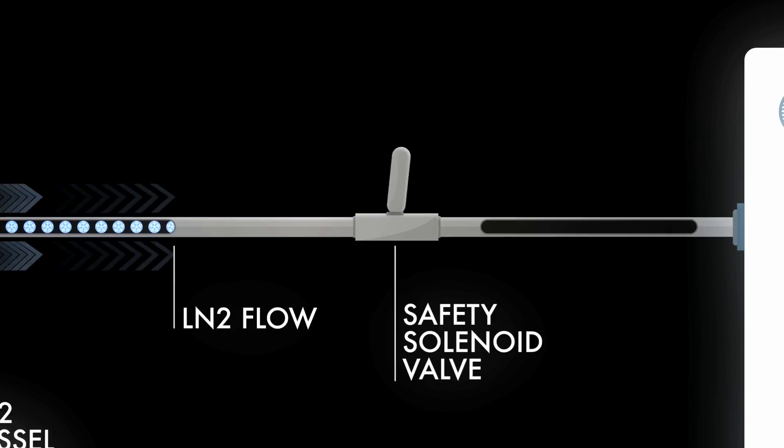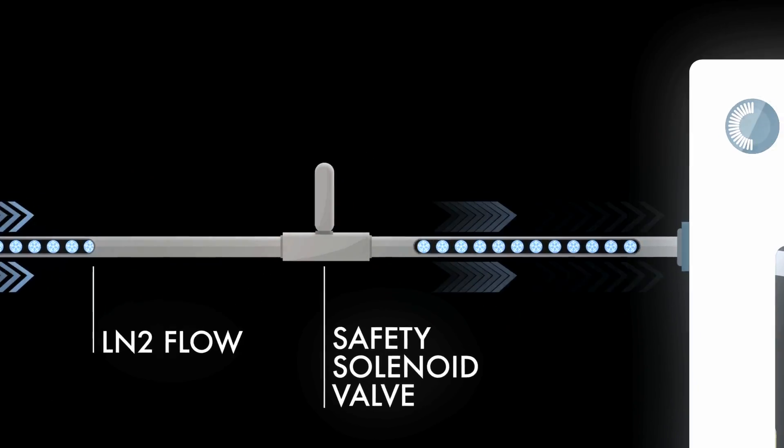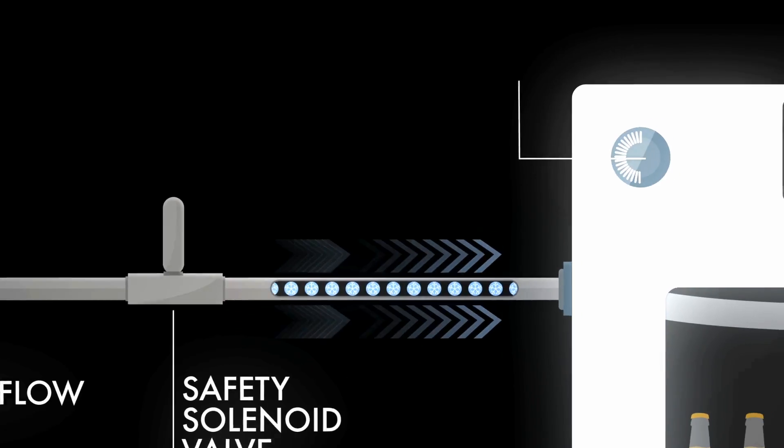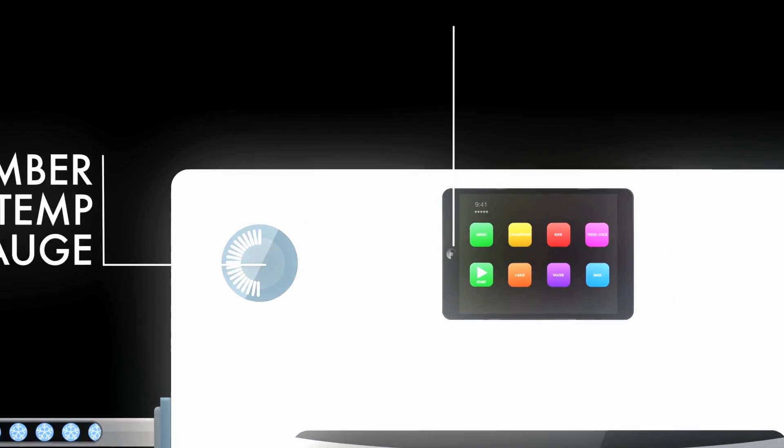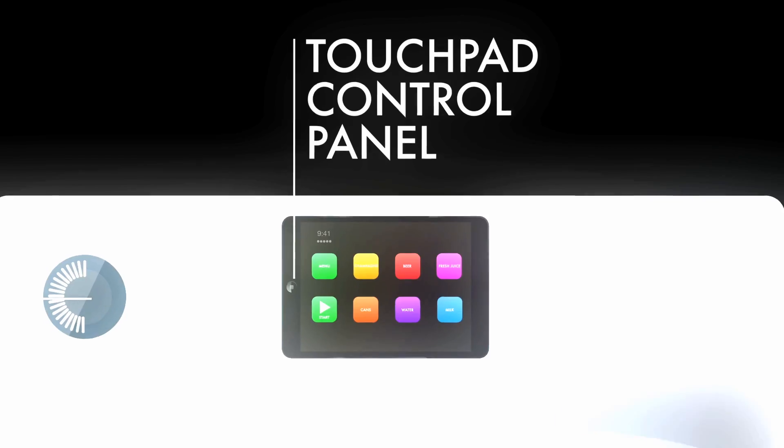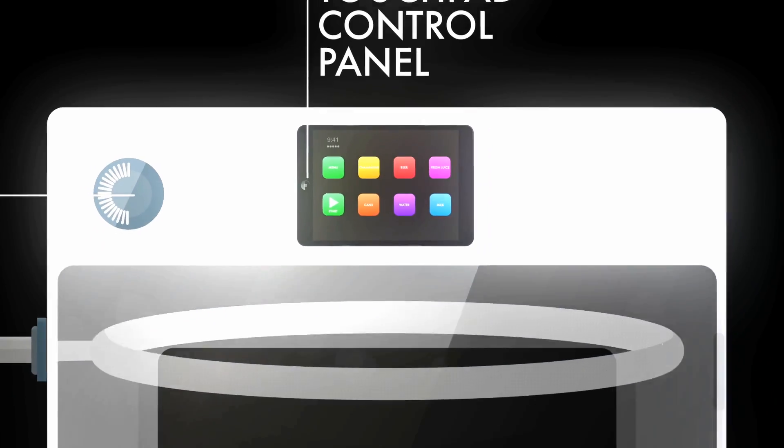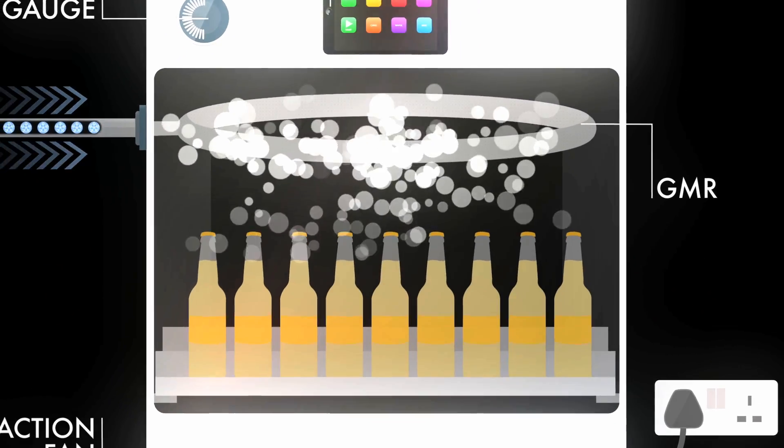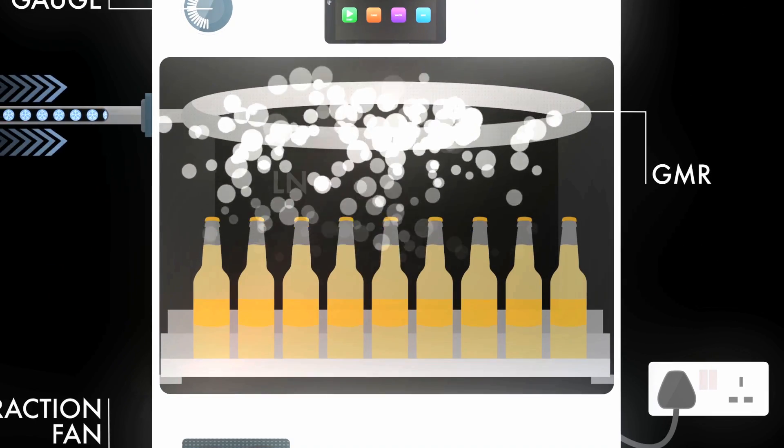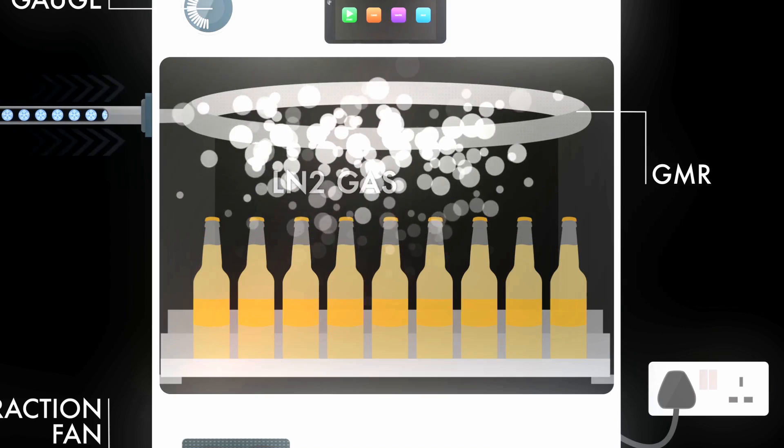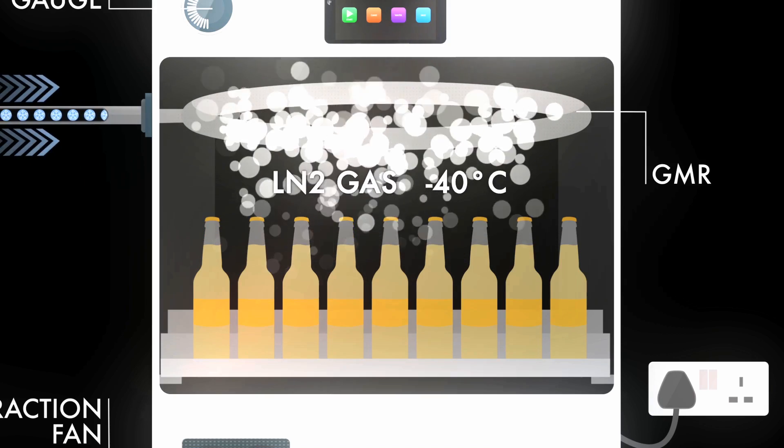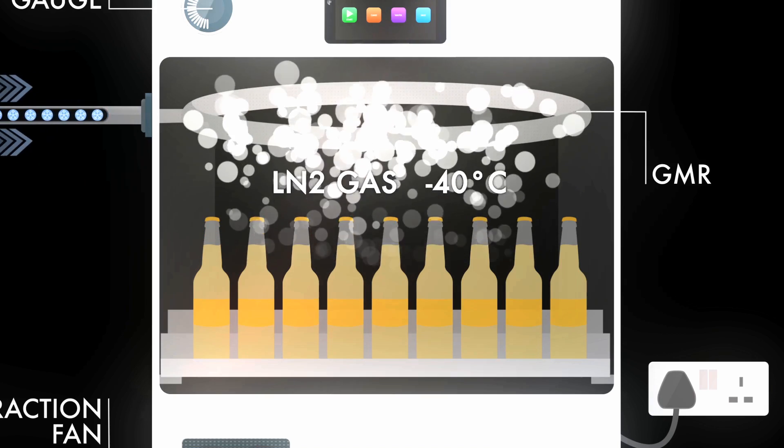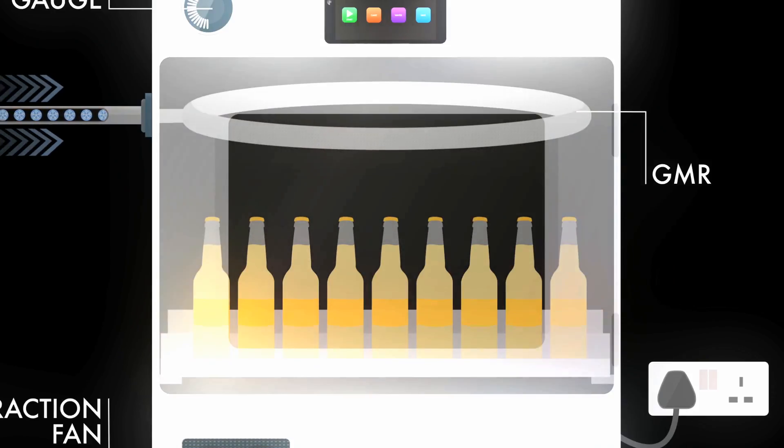The switch opens to allow the correct volume of liquid nitrogen into the chilling cabinet as selected on the proprietary smart control panel. The LN2 is atomized through the gasification manifold ring, or GMR, as it enters the cabinet, creating the minus 40 centigrade environment.